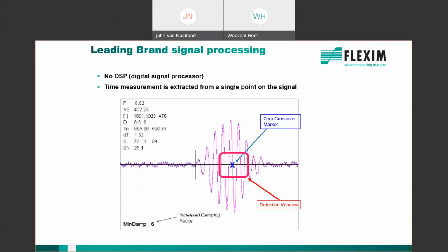Imagine over 30 days. Another amazing technology difference with FLEXIM clamp-on meters is the digital signal processing. Here is a leading brand and how they do it. What they do is they digitally impose a marker on the sinusoidal waveform. And this is what that sinusoidal waveform looks like. And this is happening multiple times per second. Through the electronics, this mark is statistically placed at the highest peak-to-peak waveform, and the mark is called the zero crossover. There is an electronic detection window where that digital mark should appear.